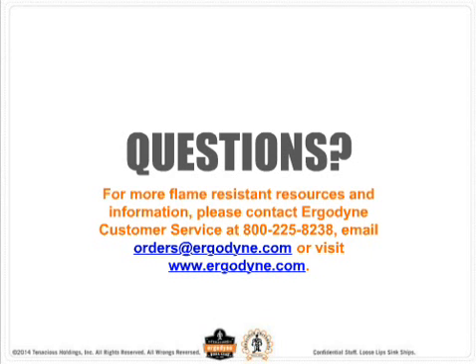There are a couple of questions here regarding materials that can go on the FR clothing, such as a non-FR logo or patch. Are those allowed? Yeah, great question. I know a lot of people want to personalize their PPE with maybe a company logo or possibly a worker name. That's a common request that comes around, especially when we talk about FR apparel. The thing is, unfortunately, the way the FR standards are written for arc flash PPE, there aren't any specific guidelines on size and materials that are acceptable for use on these products when we talk about logos. What ASTM F1506 does say is that any logos, name tags, or any sort of patches can be constructed with non-FR materials as long as the overall area is minimized on the garment. Again, it's sort of a gray area. They don't provide much more than that.